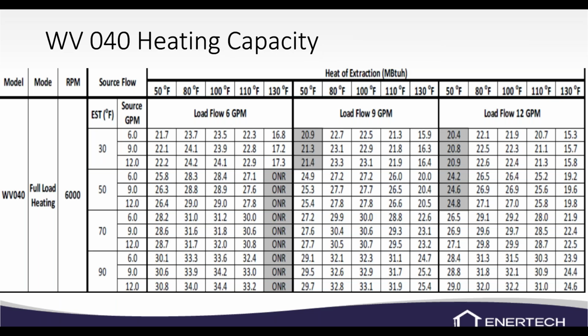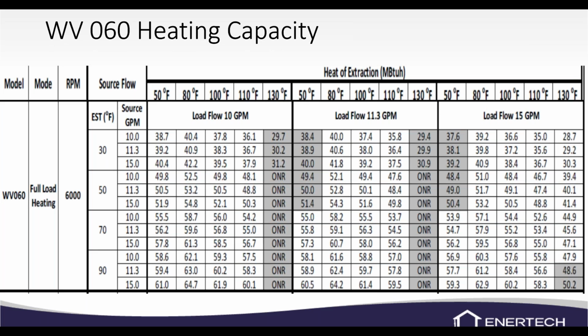If you really need to break it down to different water temperatures, other than what we showed in our AHRI ratings, in our manual we do have a heating capacity table that will show full load heating, different RPMs, and different water temperatures, and then you can see what the heat of extraction is at your different water temperatures. That's the same way for the 040 or the 060. We've really got it broken down pretty well in our spec manual there.